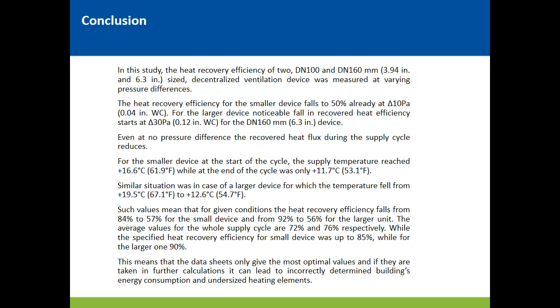If you assume that all the time this efficiency will be this 90%, then the estimated heat consumption of the building during the whole year can also differ from the actual situation, because maybe the person who calculates this energy consumption of the building will not take into account that this heat recovery efficiency will be smaller than actually stated in these data sheets.